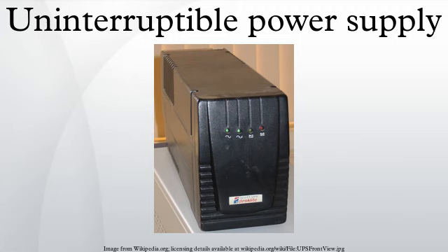An uninterruptible power supply, also uninterruptible power source, UPS or battery flywheel backup, is an electrical apparatus that provides emergency power to a load when the input power source, typically mains power, fails. A UPS differs from an auxiliary or emergency power system or standby generator in that it will provide near instantaneous protection from input power interruptions, by supplying energy stored in batteries, supercapacitors, or flywheels. The on-battery runtime of most uninterruptible power sources is relatively short but sufficient to start a standby power source or properly shut down the protected equipment.